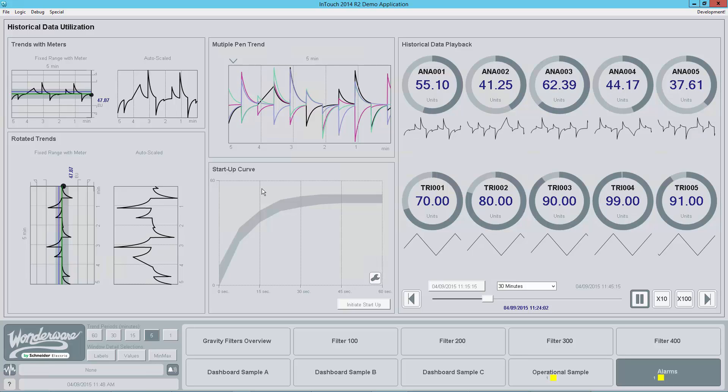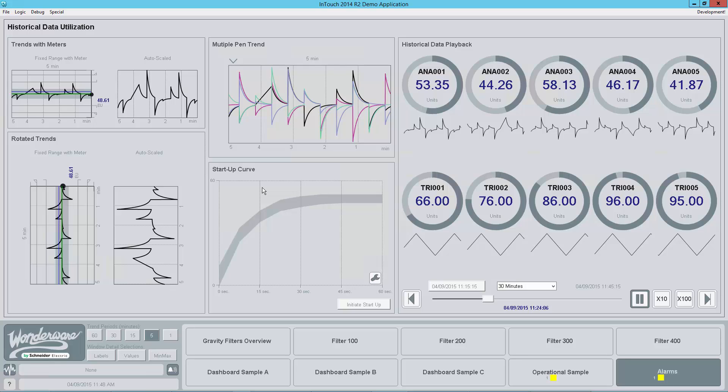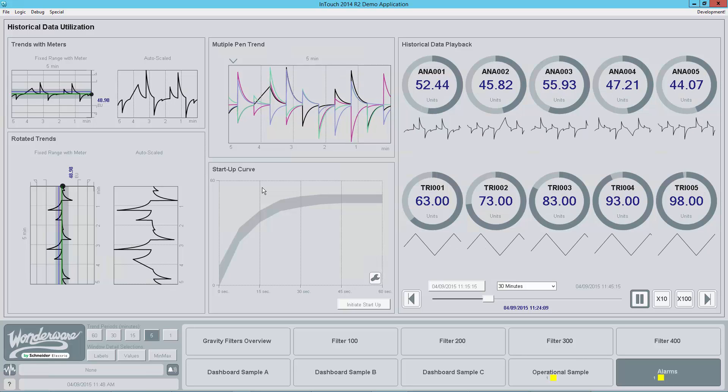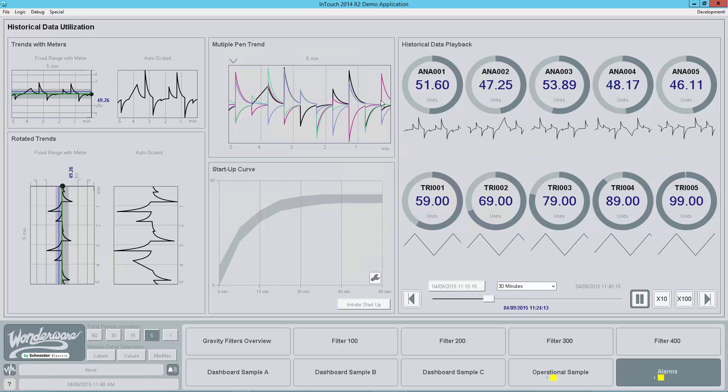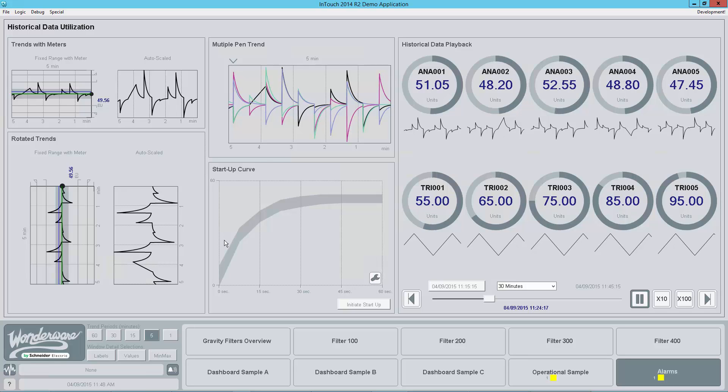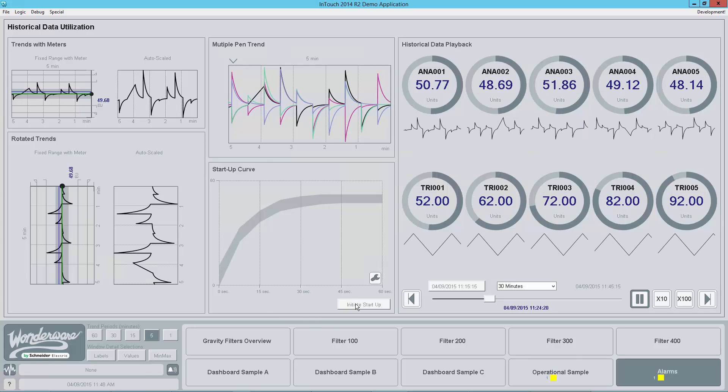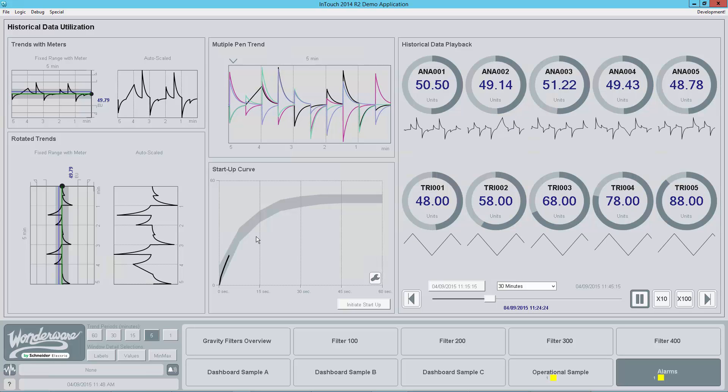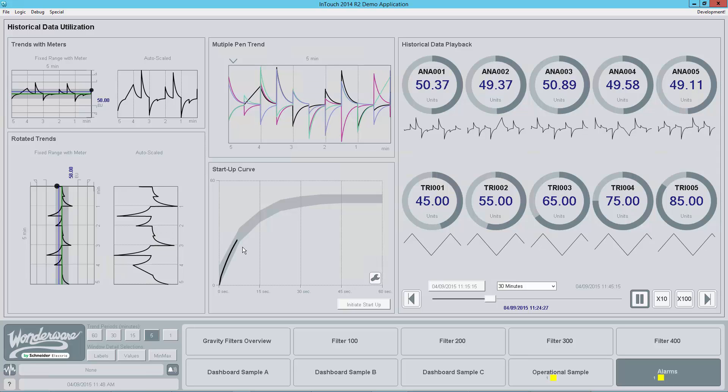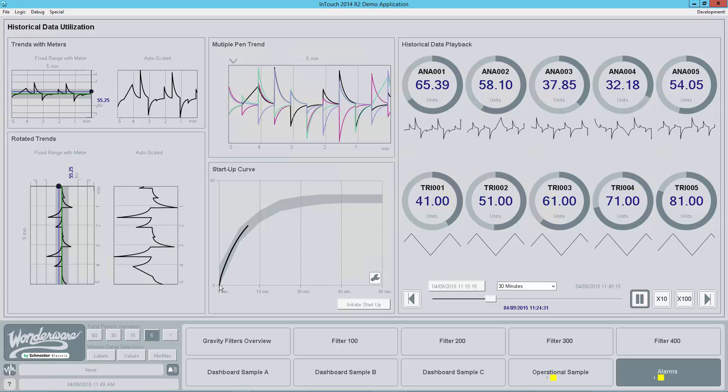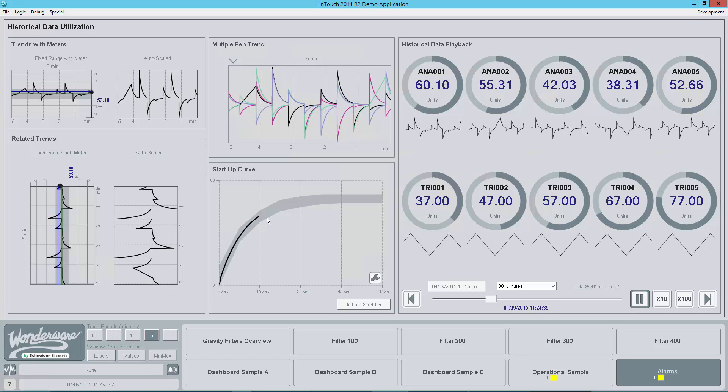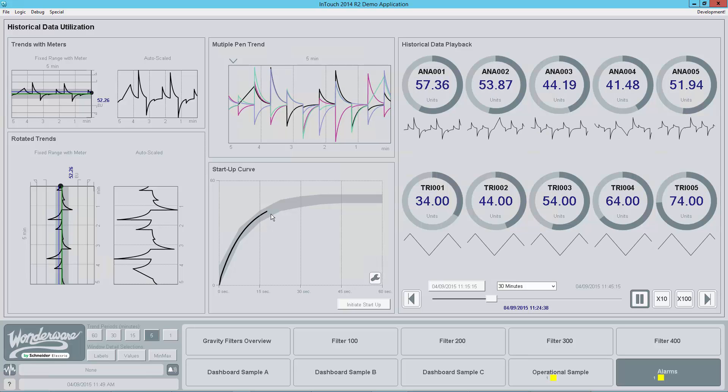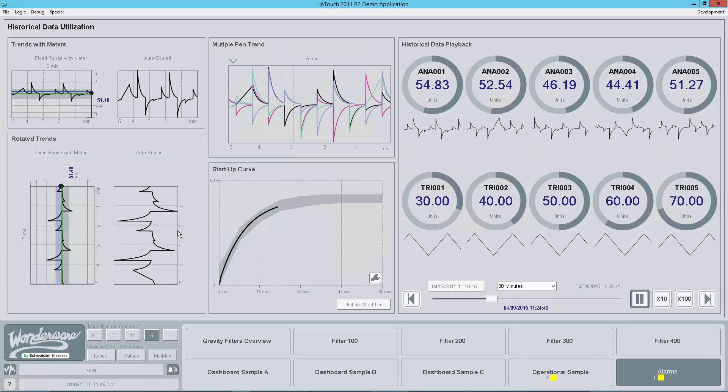If I go below here to the startup curve, this is leveraging a capability that we improved the trend pen graphic element itself. Now you can actually tell it where you want to anchor that time. Most of the trends, as you can see up here in the top, are anchored, whereas the right-hand side is now. Whereas the bottom, you can actually set a fixed time to anchor the left. And so if I click this initiate startup, what it's simulating here is the startup of a piece of process equipment. What I've done is I've linked this trend to a data variable, and I've told it to set that time at my startup time. So I can see how that data is going to be proceeding throughout my startup process. And here I'm only showing a minute's worth of data to facilitate a short video.